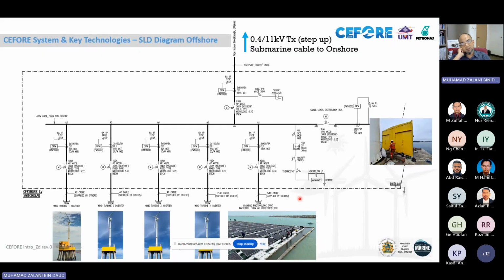Moving to our design based on the circuit diagram: we have 4 wind turbines feeding to the low voltage bus bar, with one wind turbine platform dedicated for the e-house, the powerhouse at the offshore site. So 4 feeders go to the low voltage bus, plus 1 feeder from floating solar. The floating solar generation is about 220 kilowatts, and each wind turbine generates 20 kilowatts, totaling about 80 kilowatts from the wind turbines. So overall, we have about 300 kilowatts of power generated from offshore.